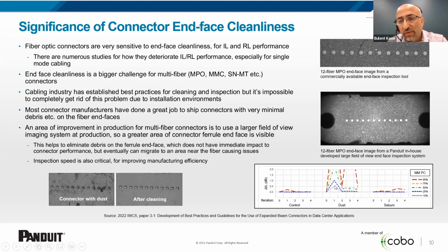And the point number 1 is after there's some dust or dirt on these connectors. And then 2, 3, 4 is after they're cleaned. The point I wanted to make is, even if you clean, the dirt and dust or debris do not always go away completely. There are still some remnants there. That's why it's important at production to make this very clear.